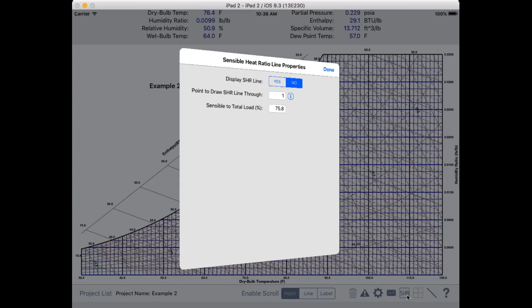But I'm going to show you one new feature here. Okay, so let me delete this point. So we have our state point here of 76 and 64. And now what I'm going to do is show you a sensible heat ratio line. So if you remember from the example, we have 7,500 BTU per hour sensible, 10,000 BTU per hour of total. So that means our sensible heat ratio is 75%. So I'm going to click SHR. I want to display the SHR line.